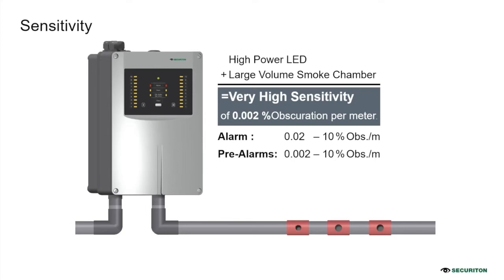No, we don't have any questions, Rohit, in the chat, but there are some questions which I would like to ask you. One of them is, why is only ASD recommended as detection technology in such applications? So valve hall, high voltage, direct current. I already explained in my previous slide that the area is too congested, and the equipment installed inside is in a random manner. It is just impossible to install any kind of detector on the ceiling or on the equipment. The best thing is that our aspiration tubes can be designed in an asymmetric manner. You can run your tube in a zigzag manner. That is why only ASD is recommended in this kind of application.